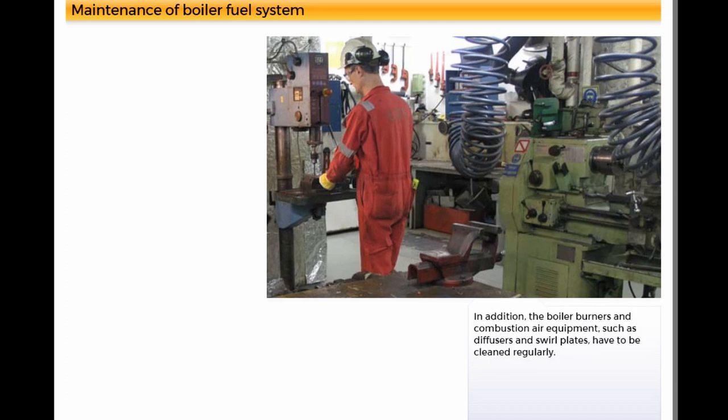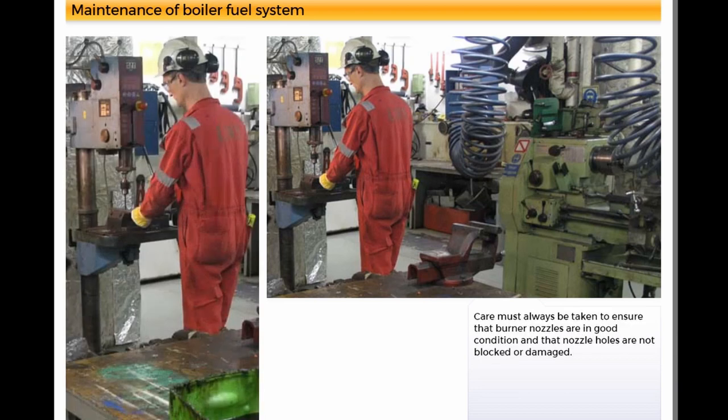In addition, the boiler burners and combustion air equipment, such as diffusers and swirl plates, have to be cleaned regularly. Care must always be taken to ensure that burner nozzles are in good condition and that nozzle holes are not blocked or damaged.